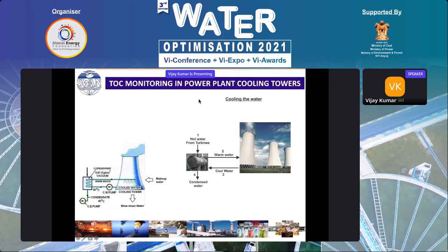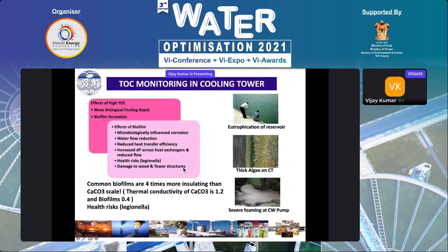Then the next subject is cooling tower water. This is the condenser, this is the inlet bay, and the cooling water is pumped into the condenser inside tubes, then goes to the tower, where it sprinkles down back into the bay, so the pressure and temperature cool-down phenomenon occurs. So this is the normal circuit. Here the most interesting thing is that it is a good atmosphere for microbial fouling. Microbial fouling will happen if you have high TOC.